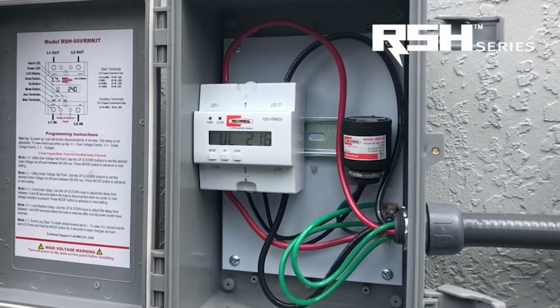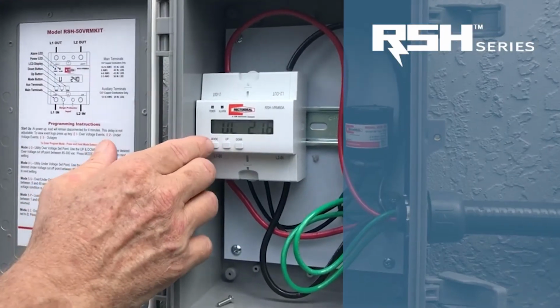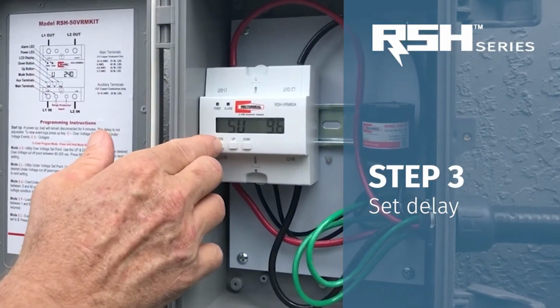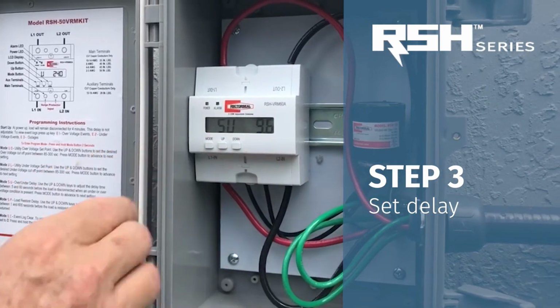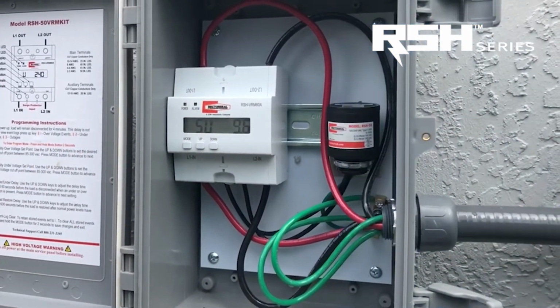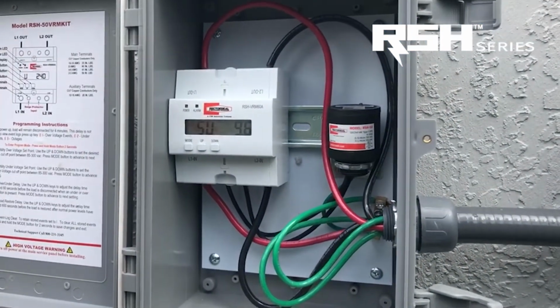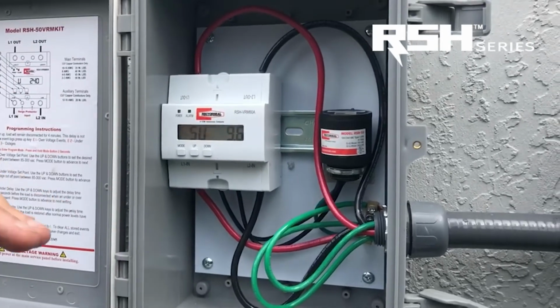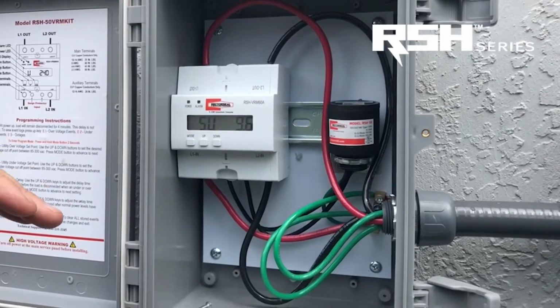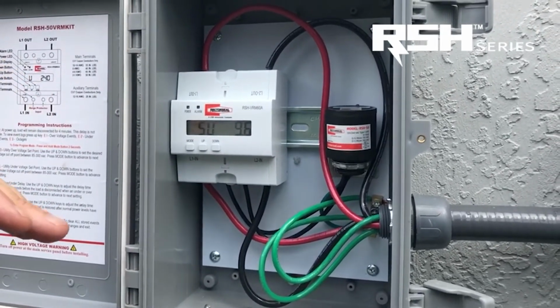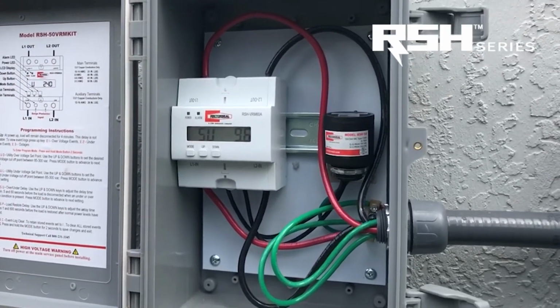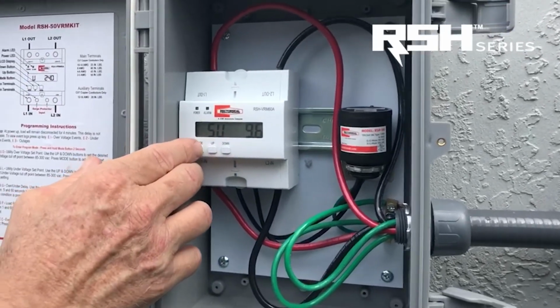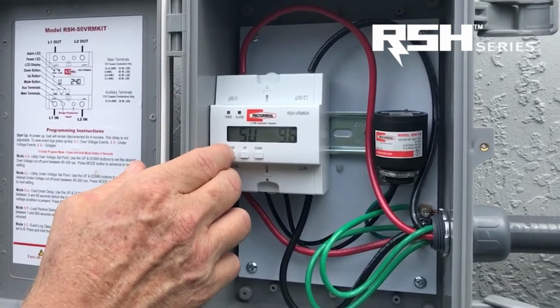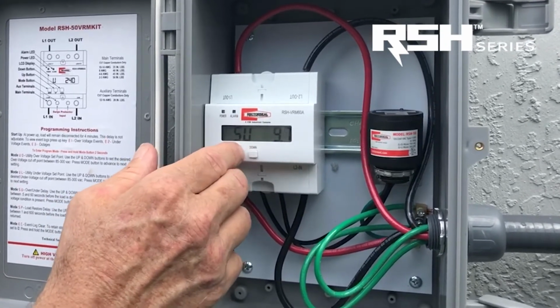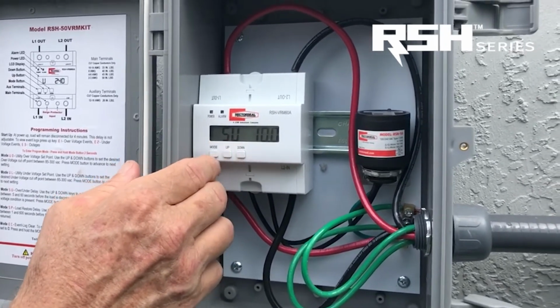over voltage events. The next thing you're going to want to do is set the delay for having the equipment shut off. So once we reach one of those thresholds, high or low, you can set the delay between 5 seconds and 60 seconds to shut power off. So we're going to set that, right now it's at 9.6 seconds. I'm just going to move that up to 10 seconds.